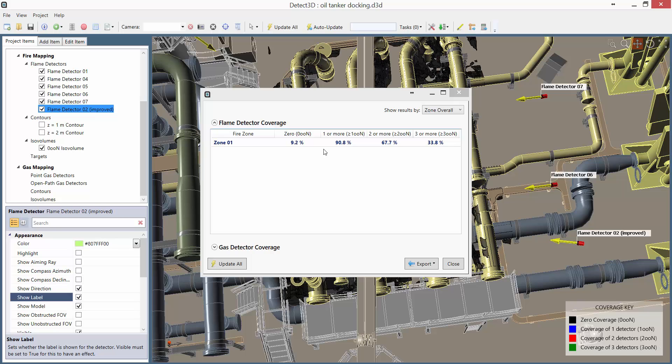But instead of eight detectors, I now have six. So it's a 25% reduction in the number of detectors, just from a quick analysis using the detector ranking tool in Detect3D. And this really shows the power of the software, not just as a coverage analysis tool, but as a design tool that enables engineers to design fire and gas detector layouts where every single detector is positioned effectively.